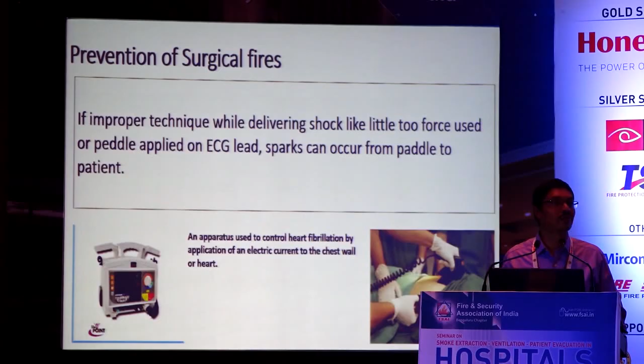So how to prevent? Remove the unneeded foot switches to avoid accidental activation. Use the electrosurgical unit in standby mode whenever you are not using it, because when you are firing, there is RF current flowing on the tip. Never use the ESU in close proximity of fuel in an oxidizer enriched environment, which I was talking about, or the fiber optic light source I was talking about. We have something called an anesthesia gas scavenging system. Basically, it sucks out all the anesthesia gas through suction and takes it out as exhaust, so we need to use it at the appropriate time. Be aware that alcohol-based preps are flammable. These are some things which we need to give as training to our entire staff, clinicians, technicians and nursing, so that we can prevent fires.